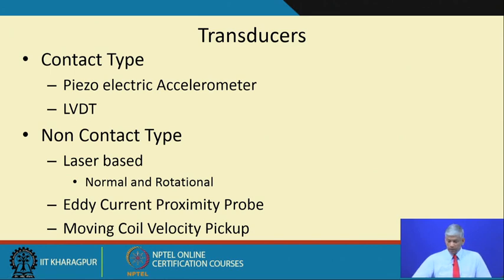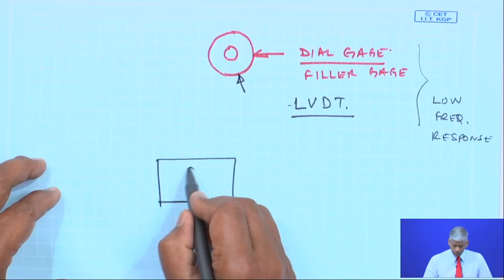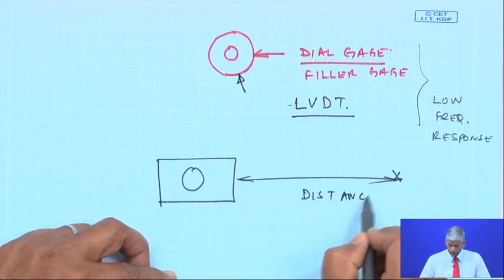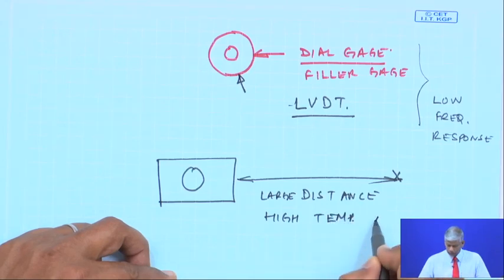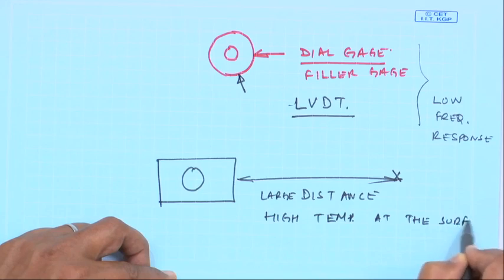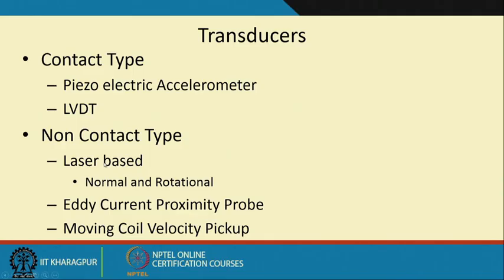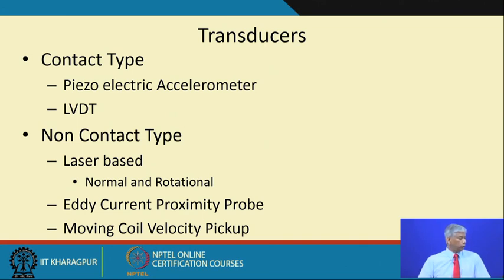However, an LVDT requires a contact stylus to make contact with the surface. There will be scenarios where you are at a large distance from the machine, or where there is high temperature on the surface — these are cases where contact-type displacement or acceleration transducers cannot be used. So there are laser-based techniques for normal or rotational measurements, and the eddy current proximity probe or moving coil velocity pick-up which are used as alternatives.